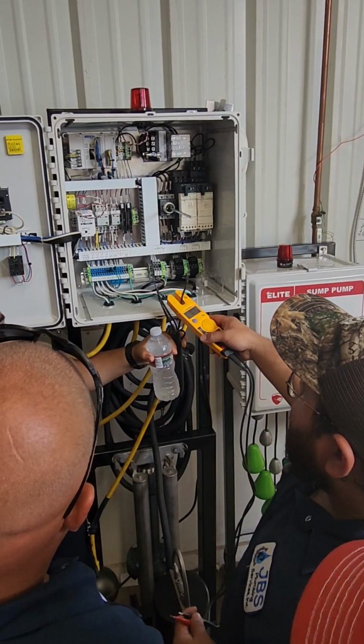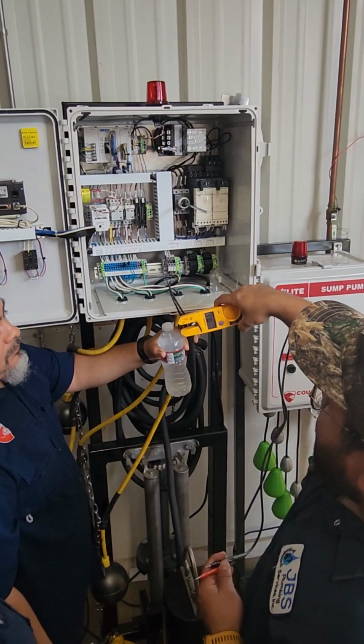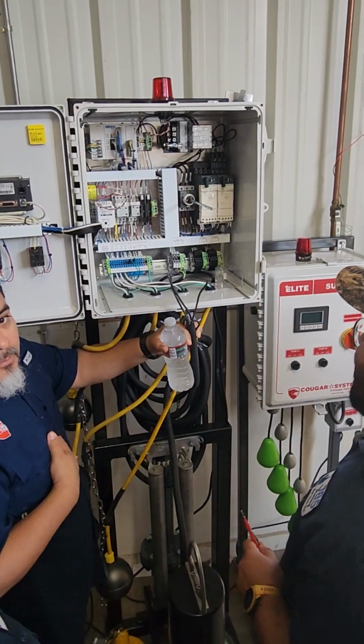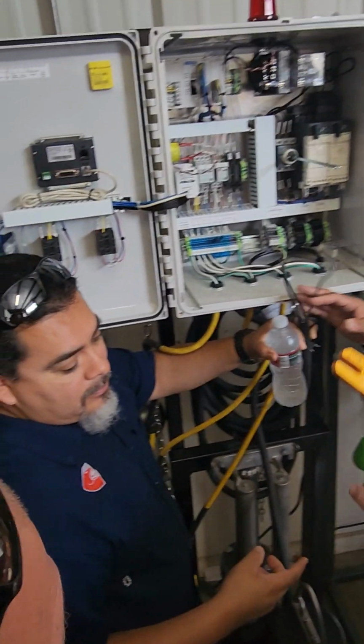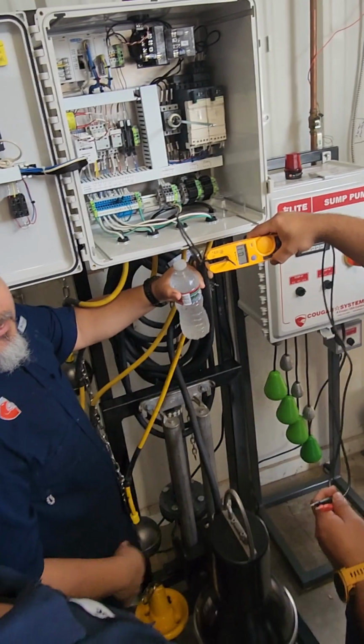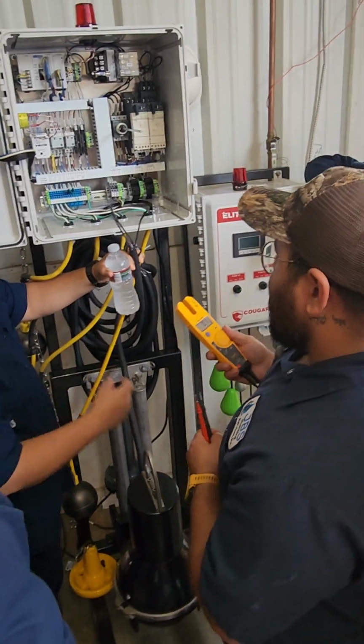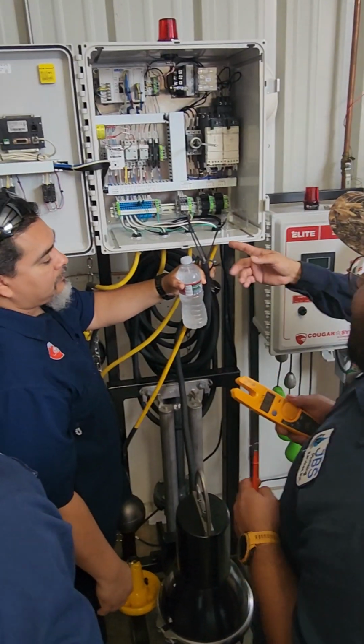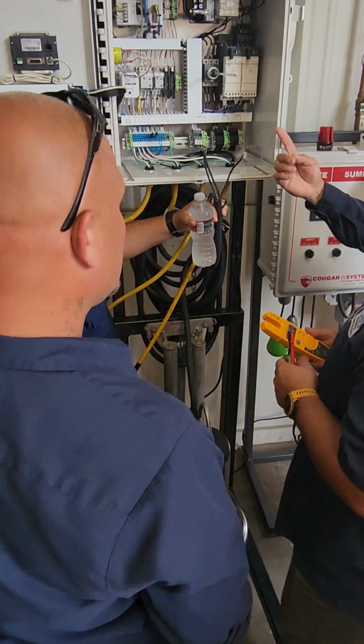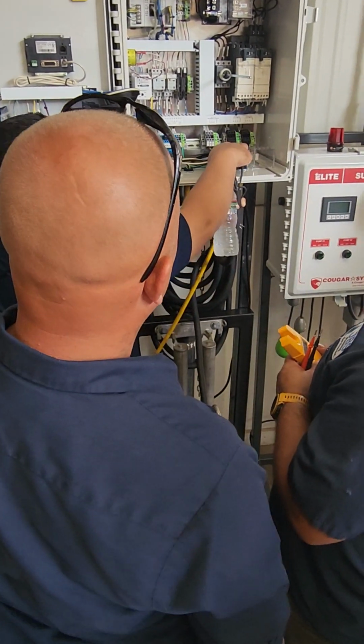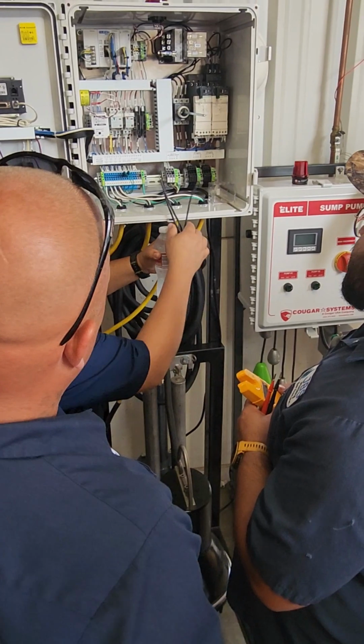How would you test it if you don't have that little clamp? What would you put your wires on? No, if they don't have this, they need one. That's what I'm saying. Your meter has to have a clamp. We have it. Yeah, we do. But you can get to this because it'll be in the box. Yes, you can wire it in there. It'll be in the same box.